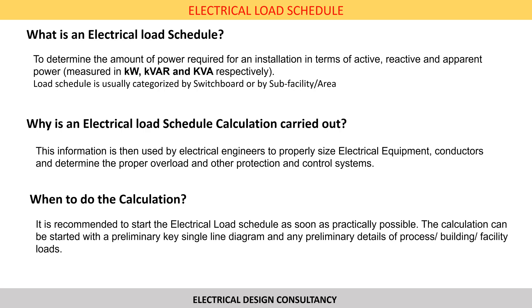Why is an electrical load schedule calculation carried out? The electrical load schedule calculation is carried out to properly size electrical equipment and conductors, and to determine the protection and control system. The electrical load schedule should be started as soon as practically possible; the calculation can be started with a preliminary key single line diagram.